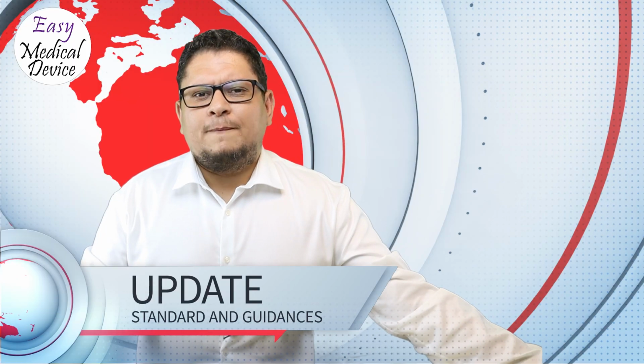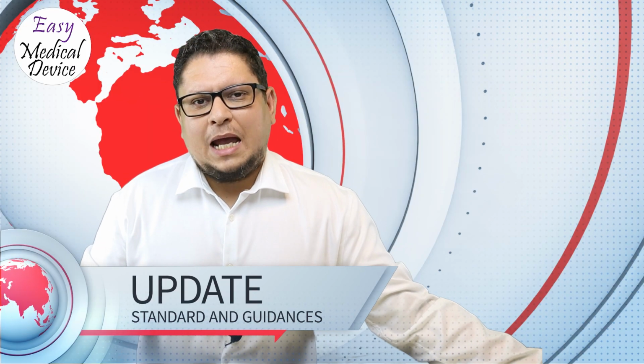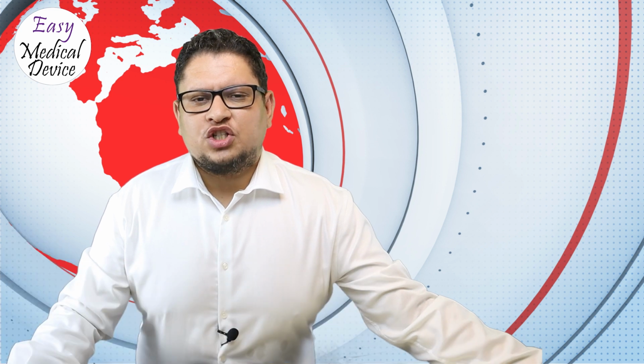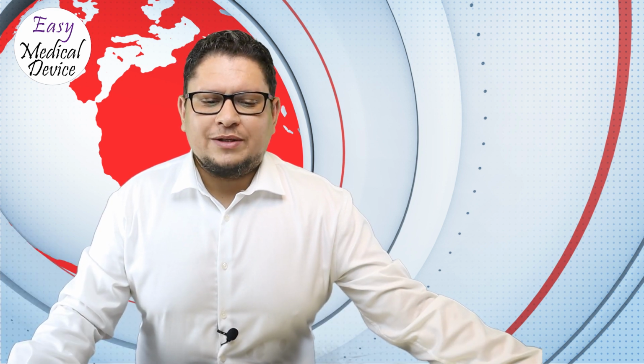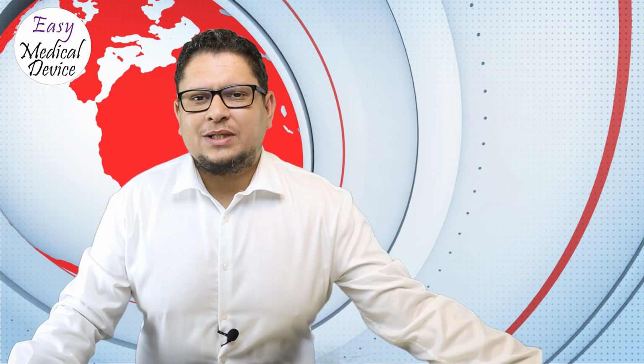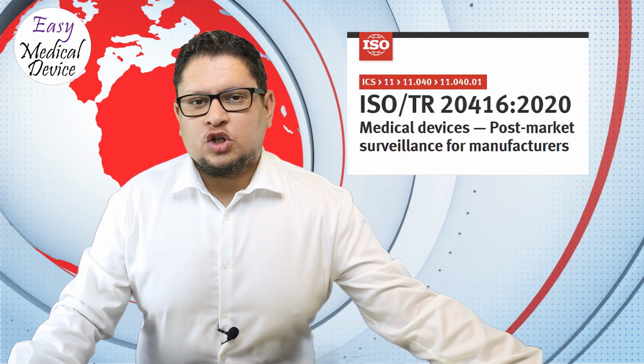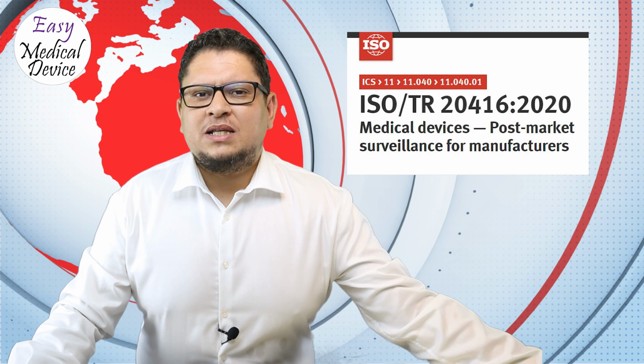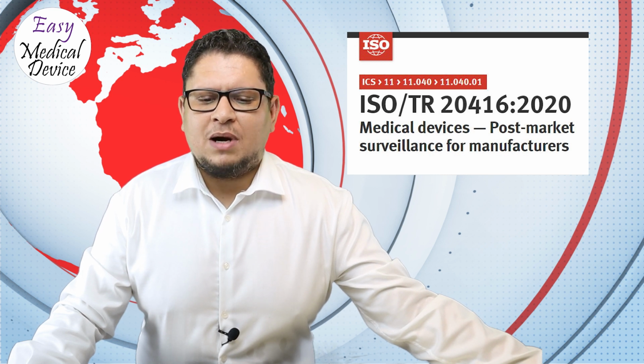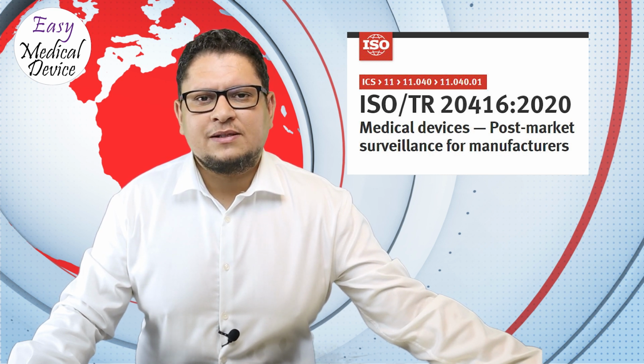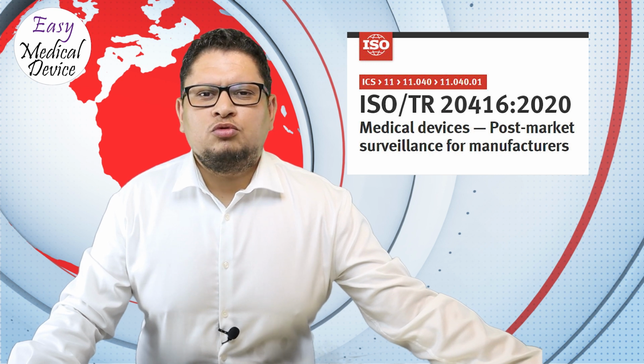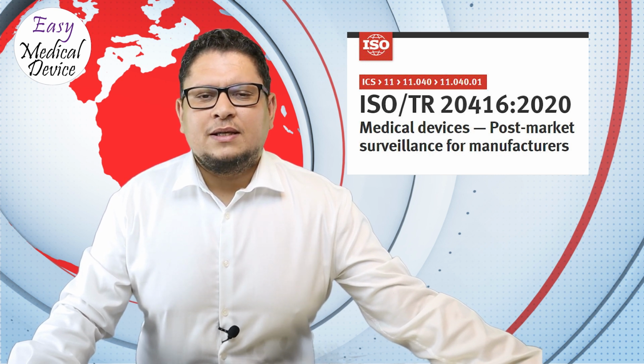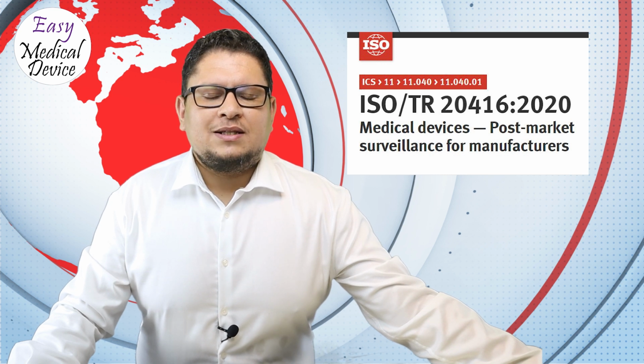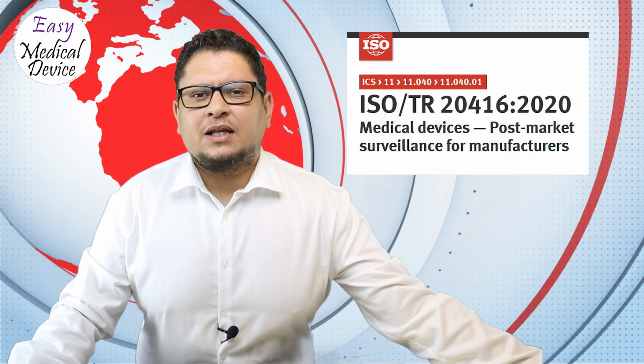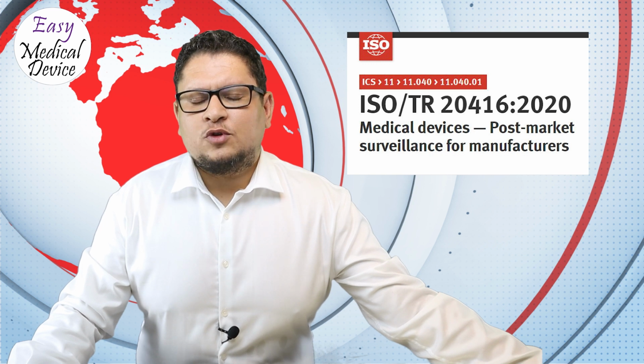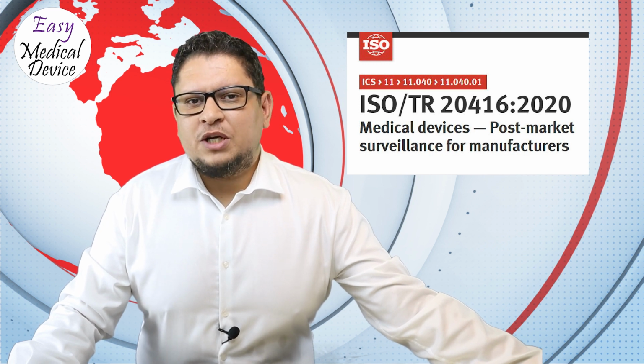Okay, so in terms of standards and guidances, what are the changes here? We have a new standard, the ISO TR 20416 version 2020 that was issued. It's a medical device standard related to post-market surveillance for medical devices. This standard can help you to build your post-marketing surveillance system. One of the changes in the post-marketing surveillance system is the fact that you should now be proactive. So you should not wait for information to come to you.